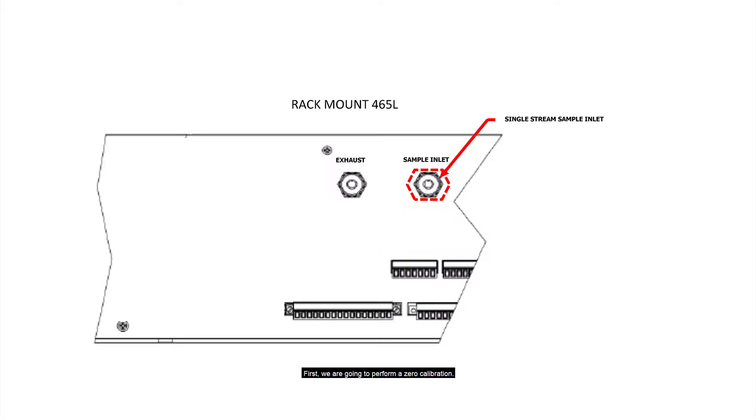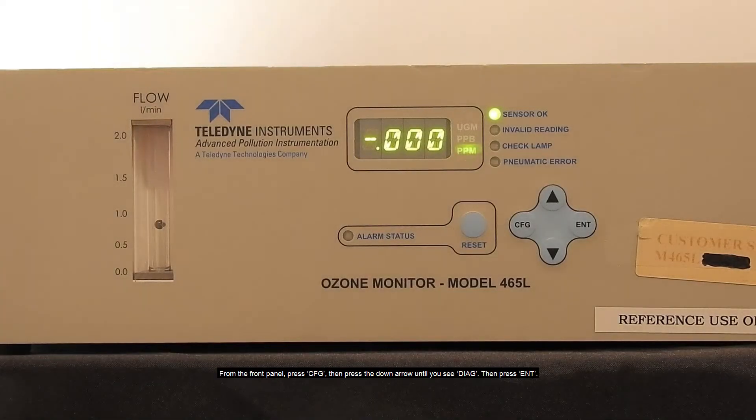First, we are going to perform a zero calibration. Start by connecting the zero air source to the sample inlet port of the 465L.